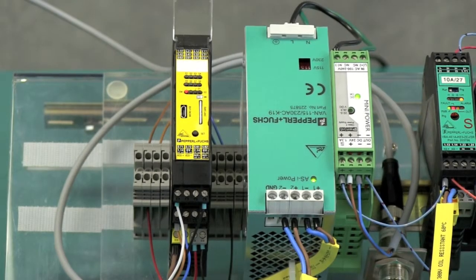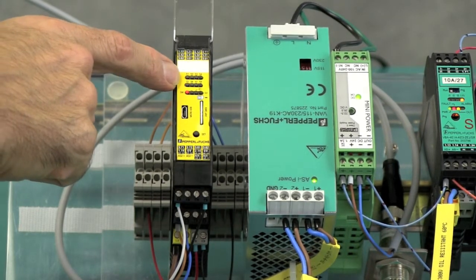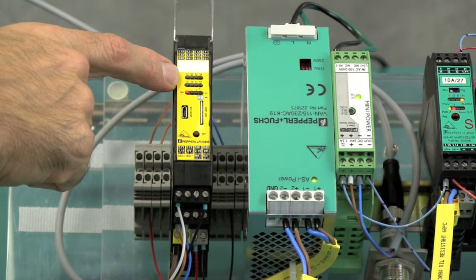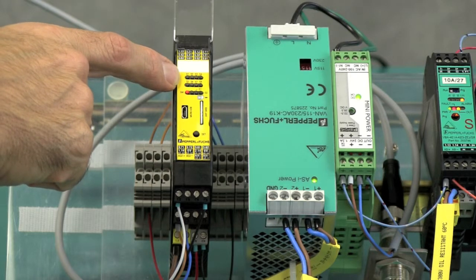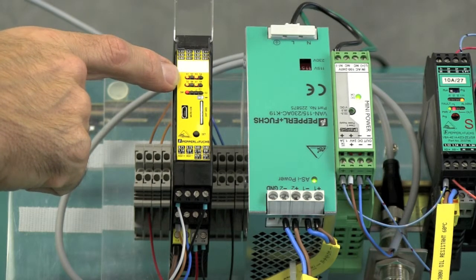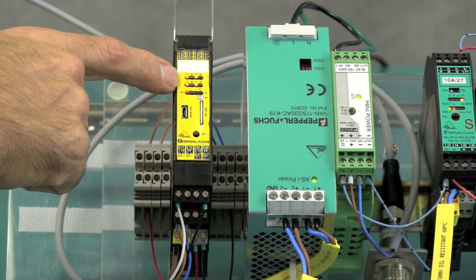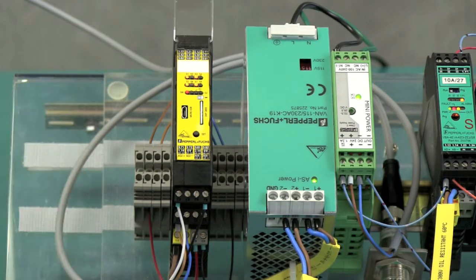If after applying power you see this LED pattern, you know that the replacement unit was not actually fresh off the shelf but already had a safety configuration. This will not work. A replacement unit must have an empty memory in order to take the chip card from the old unit.